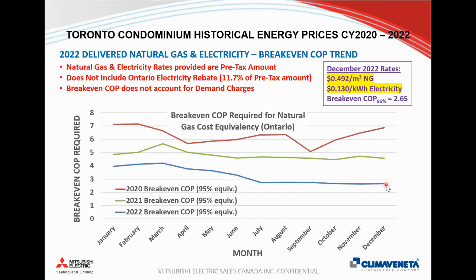And I would also like to point out that all these economic analyses that I've been providing here don't account for demand charges from the heat pump of having that peak inrush current. So that is a qualifying statement on that. That's not accounted for in these analyses.